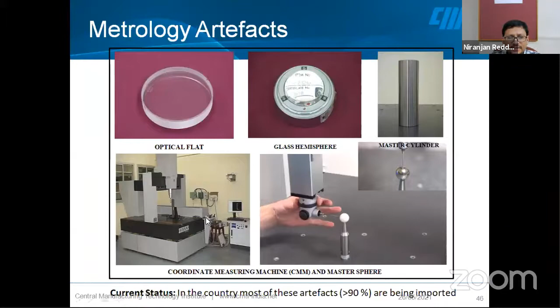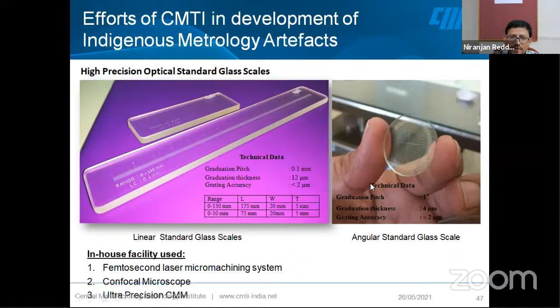Artifacts. I think in calibration, these artifacts are important. So CMTI made an effort to develop these artifacts. They are the glass scales, which have particular gratings, and these are used for the qualification of the optical measuring instruments. These gratings have an accuracy in the order of 1 micrometer. We have transferred this technology to one of the industries as well. There are linear scales and we have the graticules also. So this is one of the products from CMTI in the artifact development.